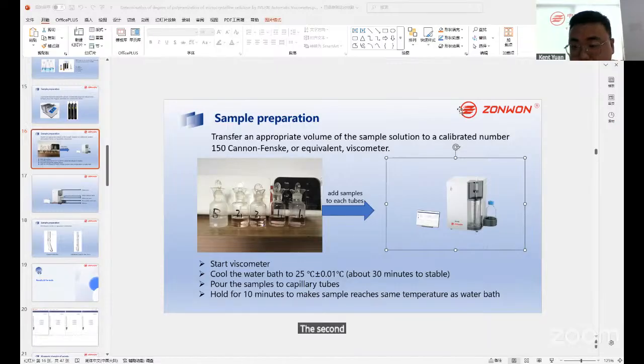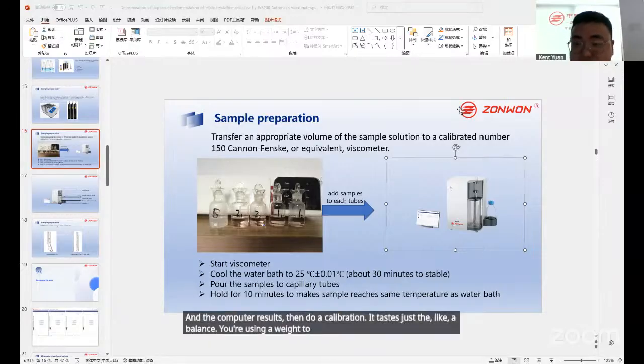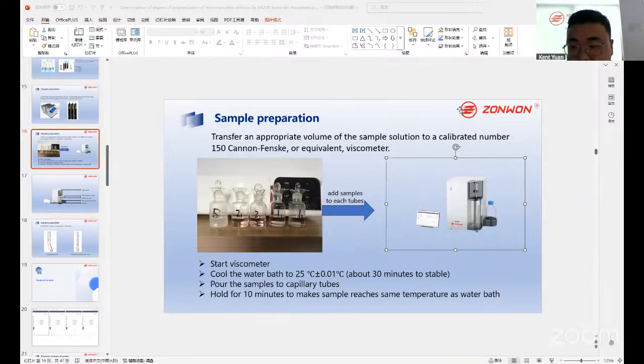The second for your daily maintenance calibration is if you are testing PET samples, they have the reference sample which has known viscosity. So we can use this machine to do the testing of known sample viscosity and compare the results, then do the calibration. It is just like a balance. You're using a weight to do the calibration. So this is my answer about the calibration.